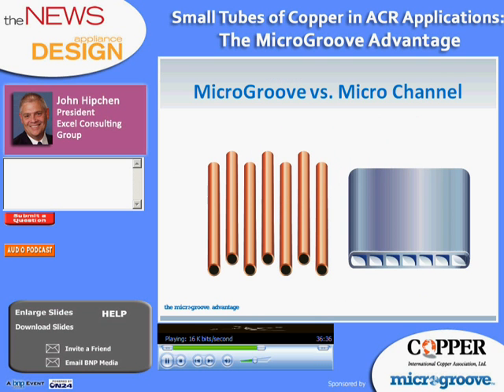Comparisons are often made between round copper tubes and aluminum microchannel tubes. Be careful here that the copper tubes in the comparison you're looking at are MicroGroove. As we've already seen, just comparing copper tubes with smooth internal surfaces to enhanced internal surfaces shows big effects. So comparing conventional, larger diameter, smooth copper tubes to aluminum microchannel tubes would no doubt show favorable results for the microchannel. However, if the comparison is made to smaller diameter copper MicroGroove tubes, you'll find that the copper tube is not only competitive, but it's often superior.